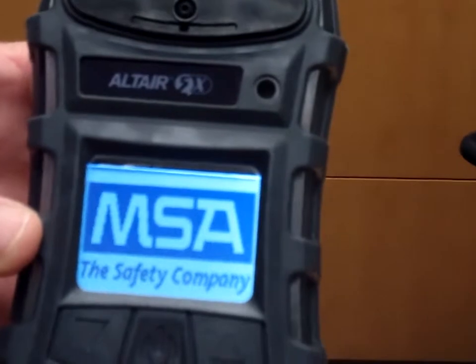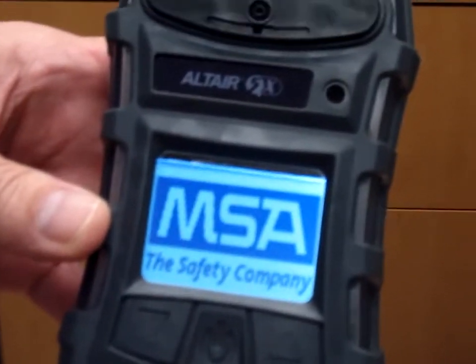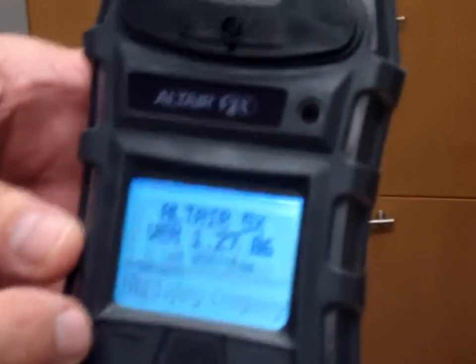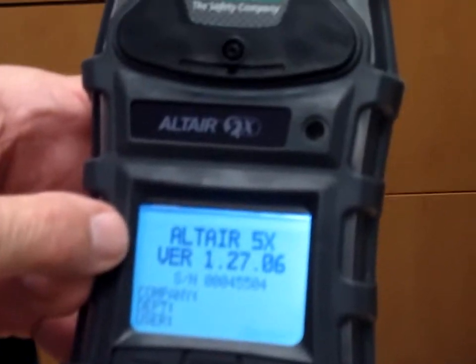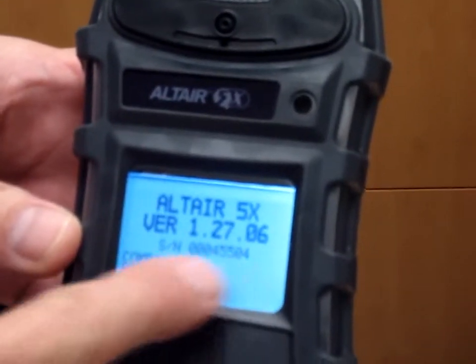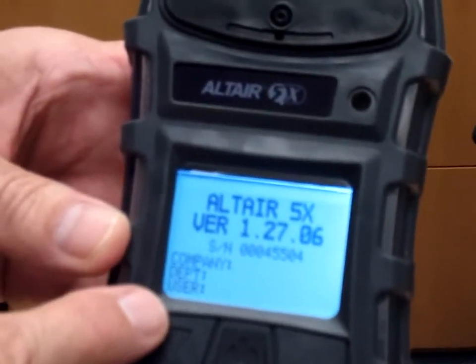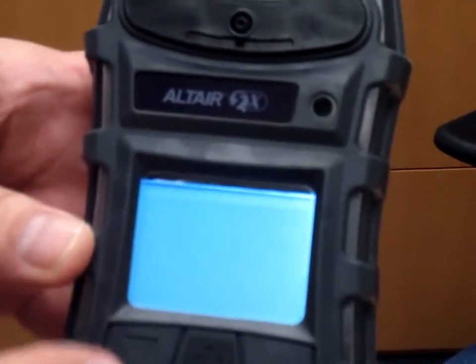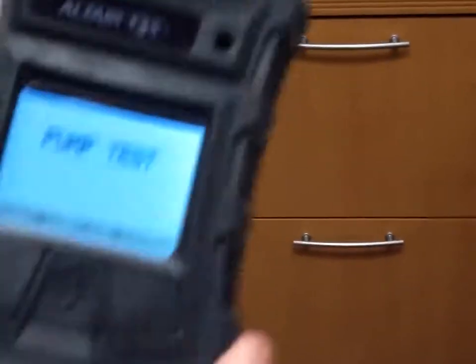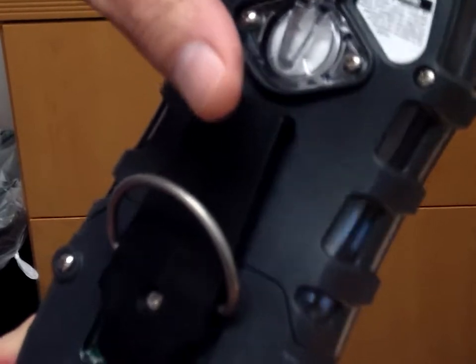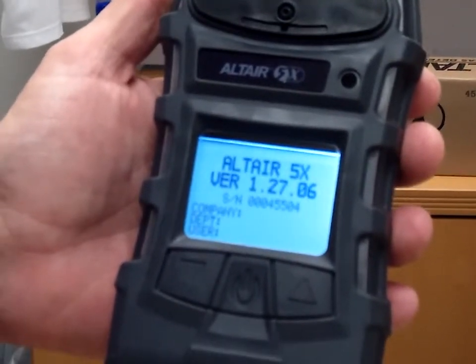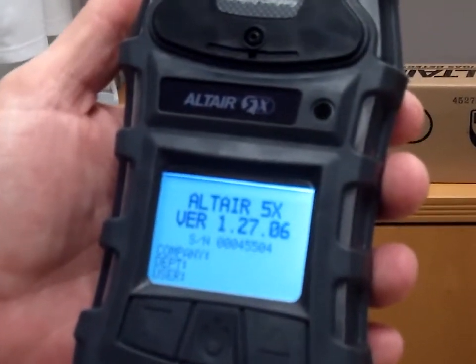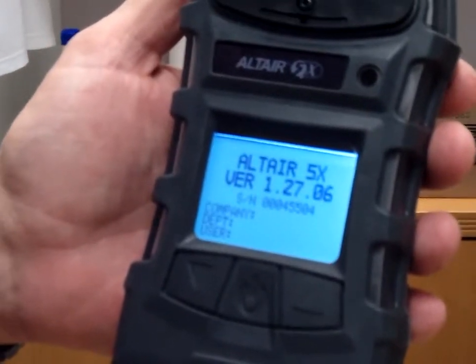At this point it'll take about 60 seconds for it to come up and give us the rest of our software version on this unit, and the serial number of this unit will display. As you can see, you have the ability to input the company and department. At this point it's asking us to do a pump test. All you do is turn around, put your finger over the back of it to make sure that the pump is secure and doesn't have any leaks. Pump test pass, and then it's going to continue to operate and get into the operation mode.